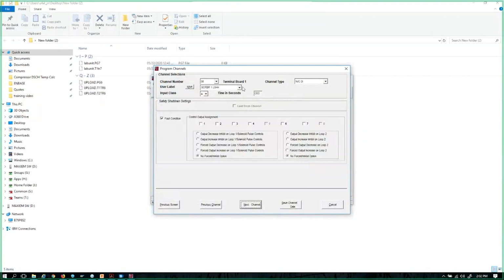Next channel is channel 8. It's also a normally closed digital input. We can see that it's scrubber number 1, LSHH, so a high liquid level. And if we count, we're probably going to see that there are more than 9 characters here. But this is not an analog channel. I'm sorry, this is a digital channel, and digital channels are not the same as what I was telling you earlier about having 9 characters or less for the analog channel. So you can put as many characters here as the software allows. We can see it's a class A. We also can see that we can turn on digital outputs with a discrete channel.